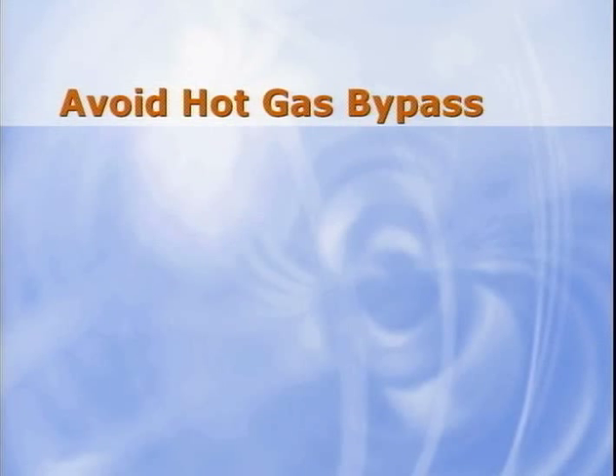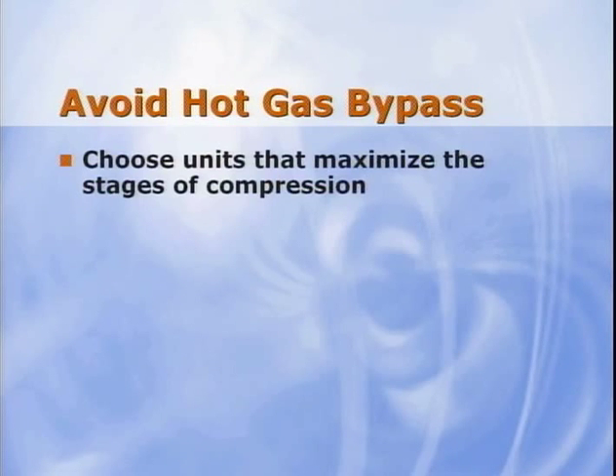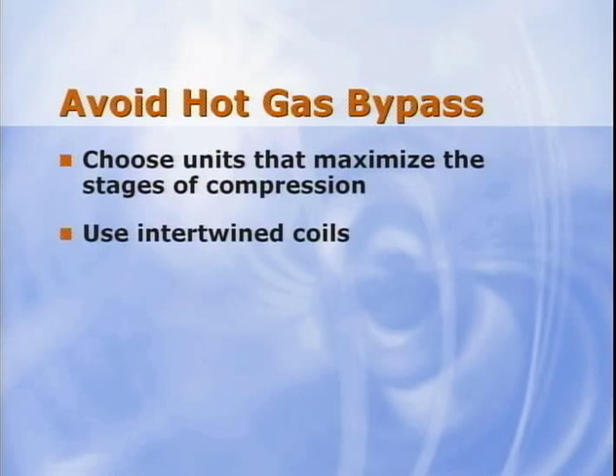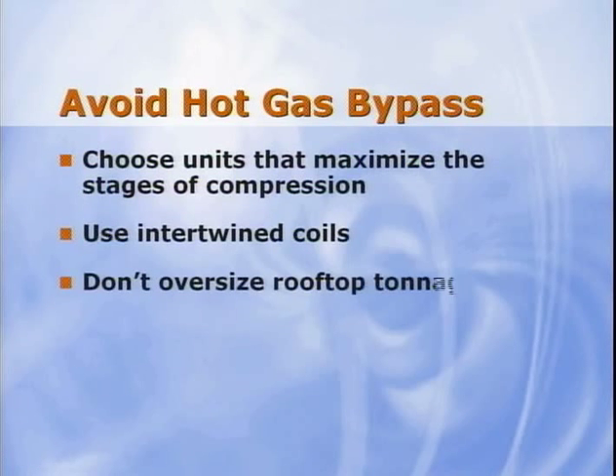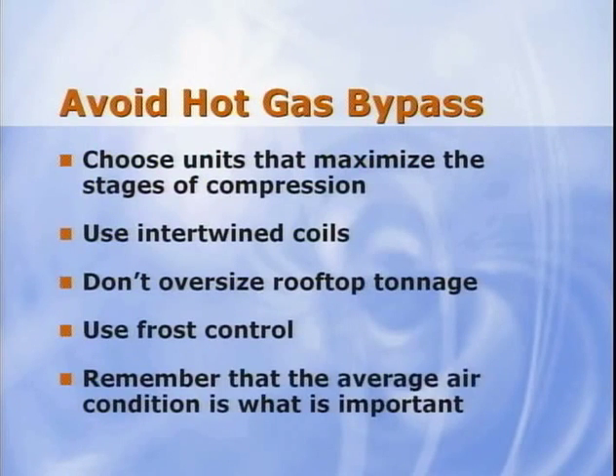That probably means it needs to be an electronic hot gas bypass system which is able to control with some accuracy. So that we provide sustainable systems for the future, and so that hot gas bypass can be avoided as often as possible, choose units that maximize the stages of compression, choose intertwined evaporator coils, never oversize rooftop tonnage, and protect against frosting conditions with evaporator defrost or frostat. And remember that the average supply air condition is what is important.